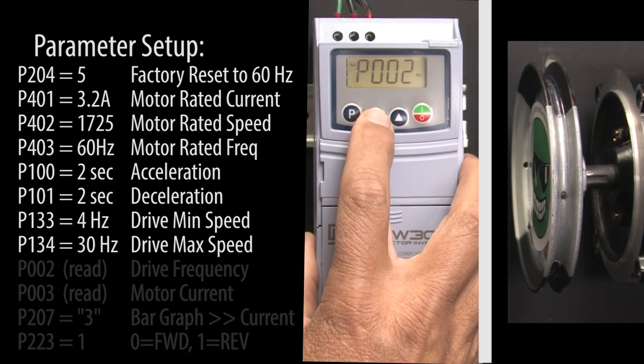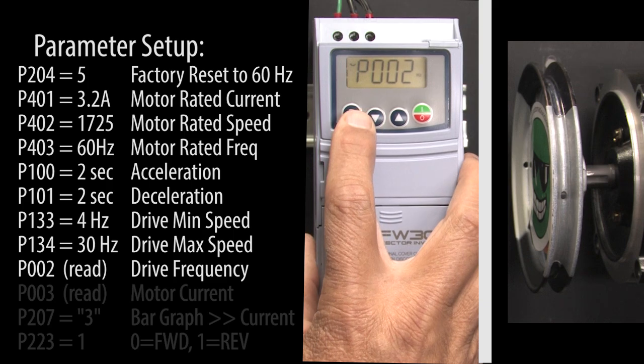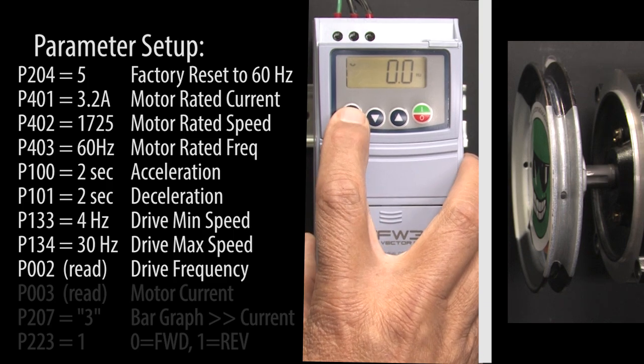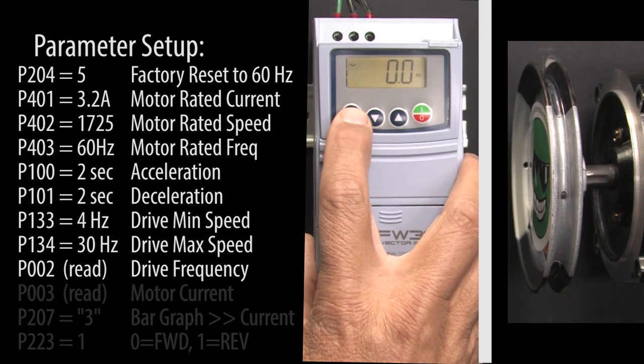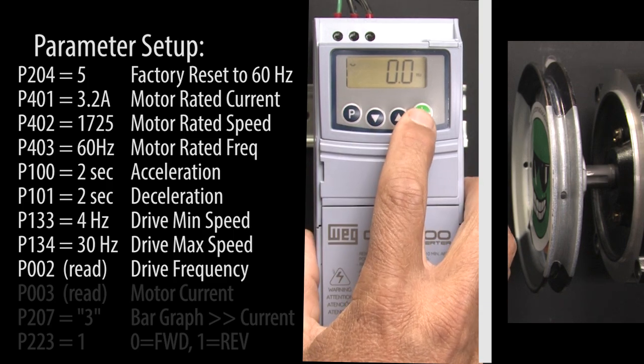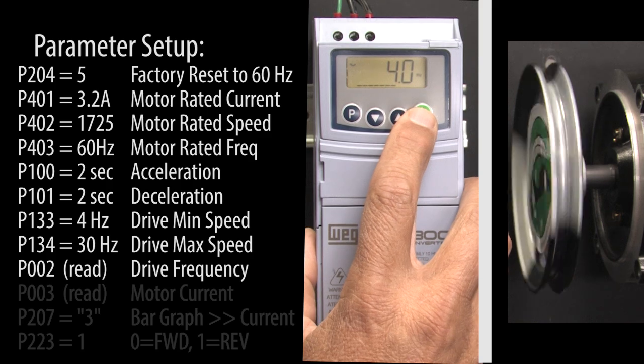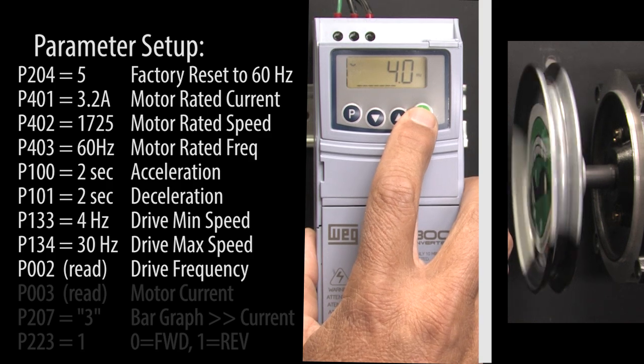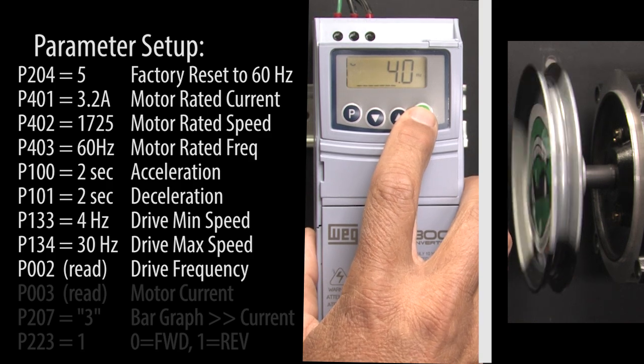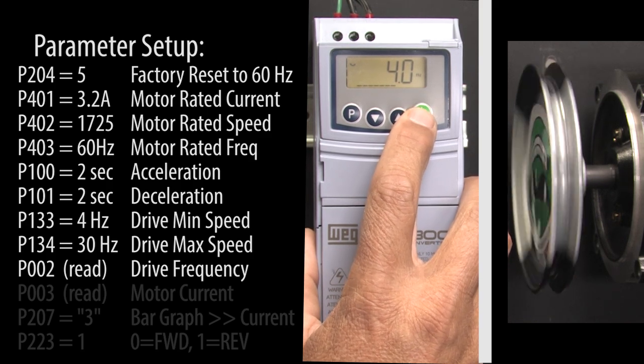Scroll to parameter 2, which shows us the drive's output frequency, and press the run/stop key to start the motor. And sure enough, the drive ramps the motor to the 4 Hz minimum output frequency we just entered. Perfect.